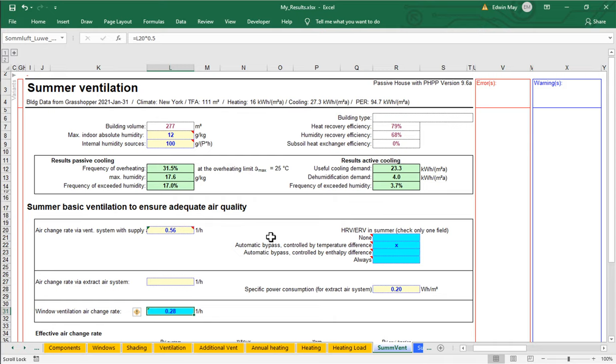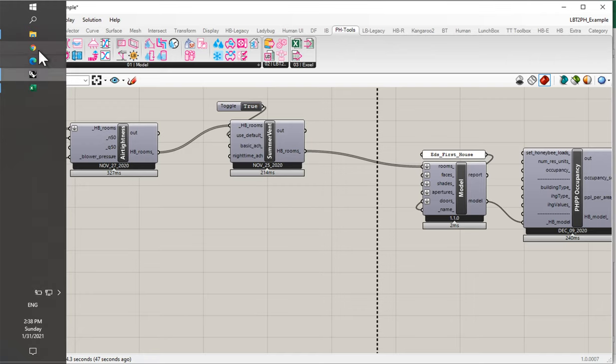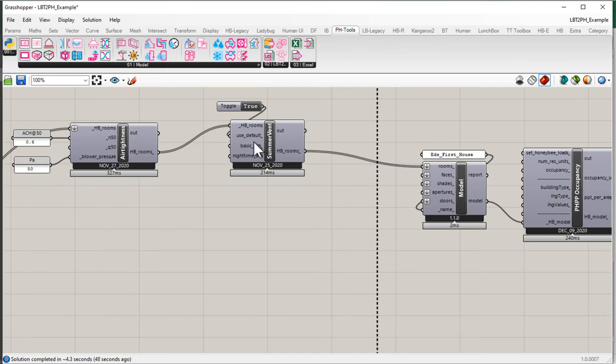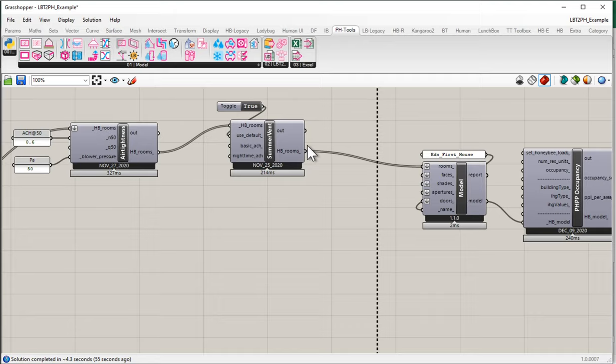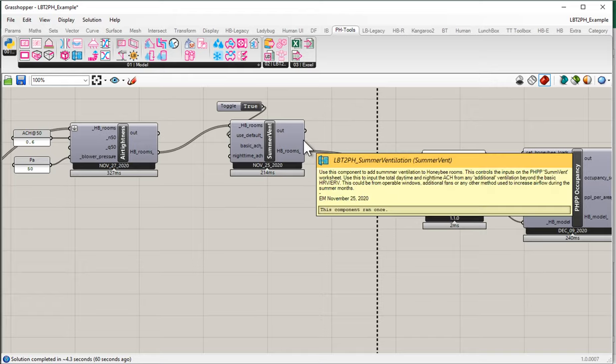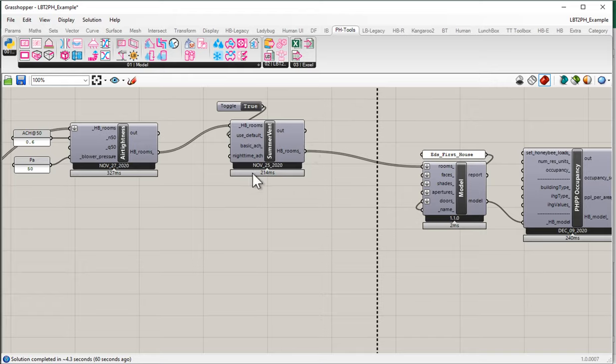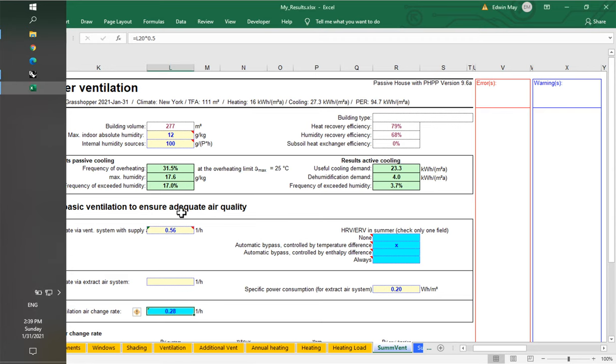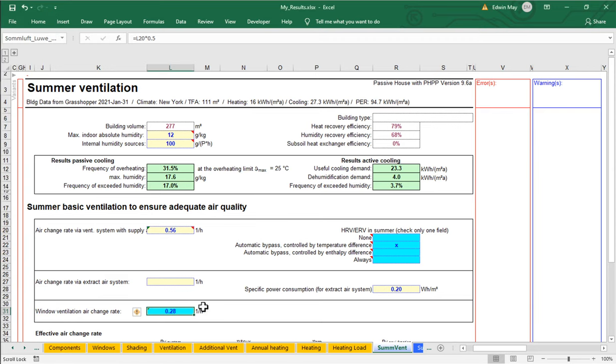So the 0.28 represents that minimum. By default, maybe we should rename this from default to use minimum. This is going to set you to the least amount of operable ventilation that still allows you to meet the hygiene requirements of Passive House certification. But you might want to add additional ACH for the purpose of cooling. So in order to improve your cooling situation, maybe you might bump that up even higher on the night or something like that. But this would be a very conservative estimate of your cooling ability through your operable window ventilation.